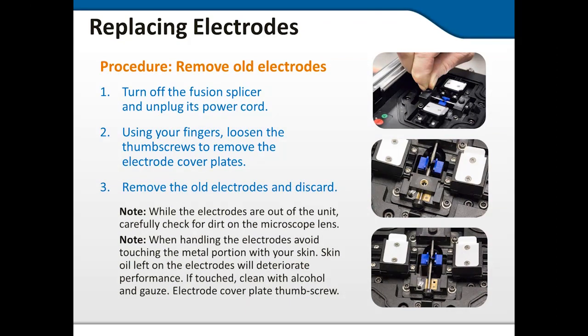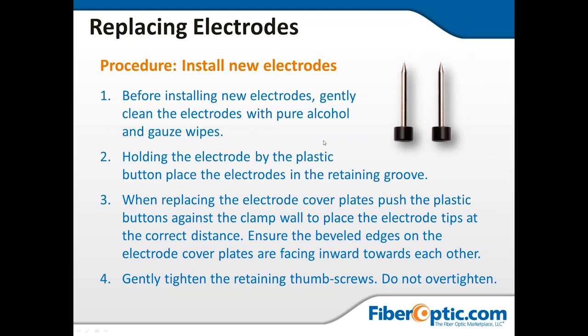Electrode cover plate thumb screws. Installing new ones. This is very important. Before installing new electrodes, gently clean the electrodes with pure alcohol and gauze wipes. Hold the electrode by the plastic button. Place the electrodes in the retaining groove. When replacing the electrode cover plates, push the plastic button against the clamp wall to place the electrode tip at the correct distance. Ensure the beveled edges on the electrode cover plate are facing inward towards each other. Gently tighten the retaining thumb screw. Do not over tighten.